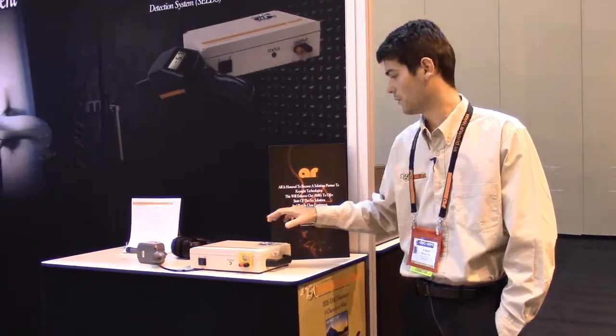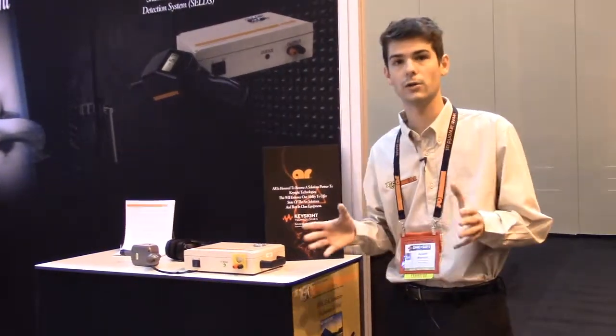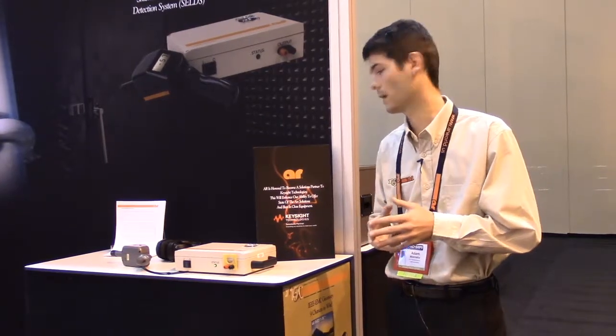The system is designed to run a current along the surface of the EMI enclosure and detect the small magnetic fields that are formed at breaks or discontinuities in the chamber.